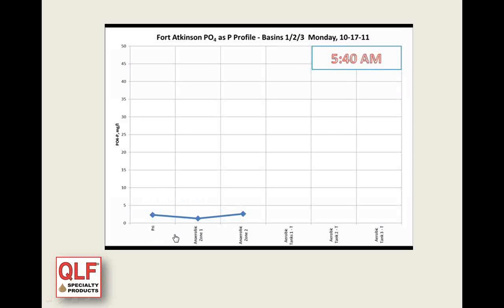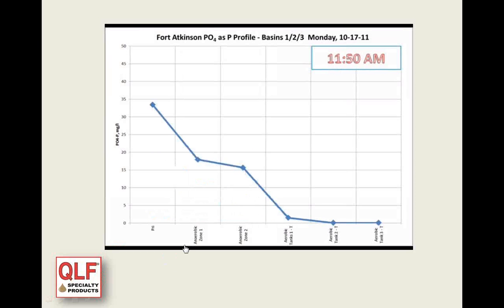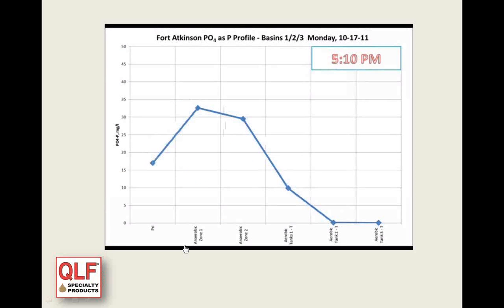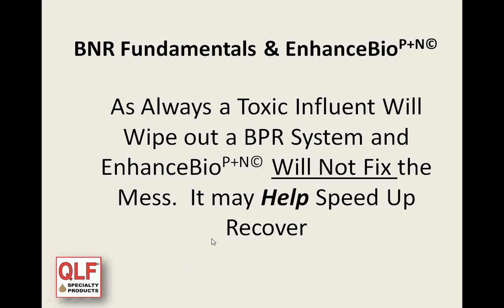Watch what happens as time progresses during the day. You can see it starting to rise, it jumps way up, and then comes back down as the day progresses. And as always, a toxic influent would wipe out a BNR system. EnhanceBio is not going to fix a problem like that. It may help speed the recovery, though.